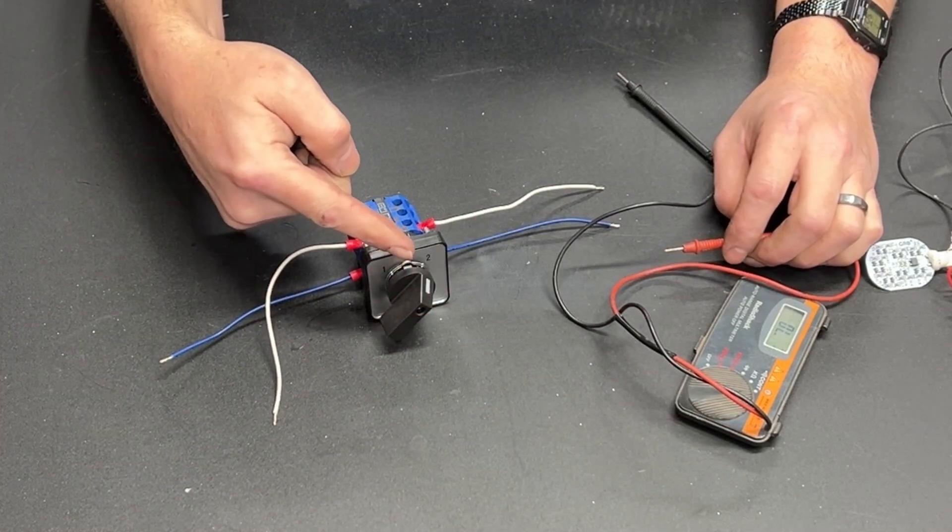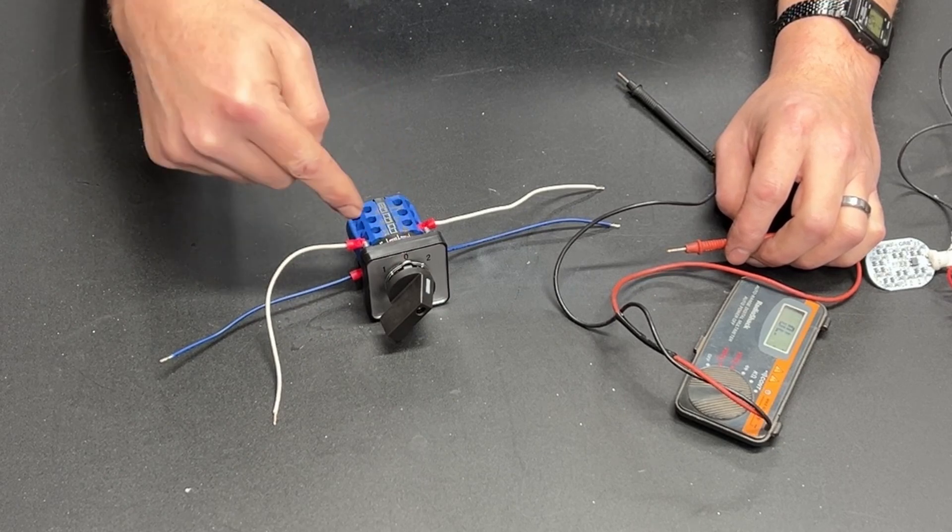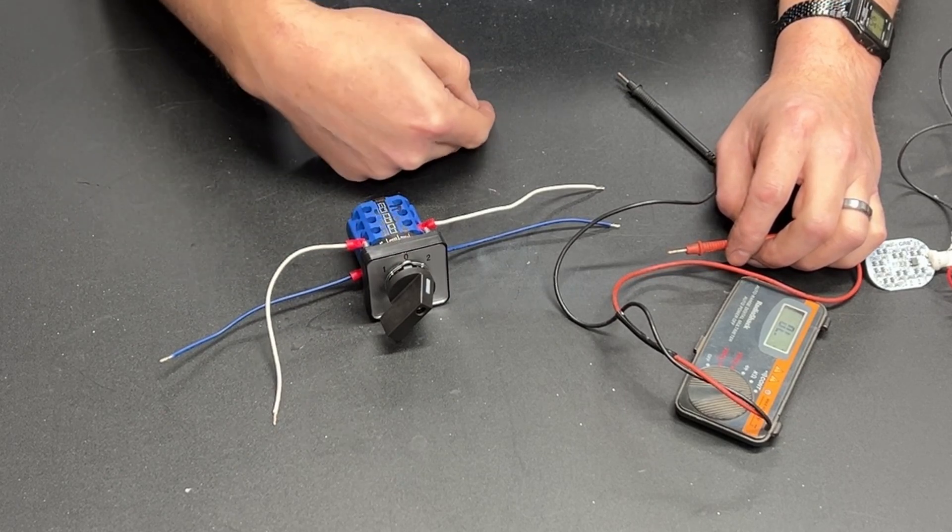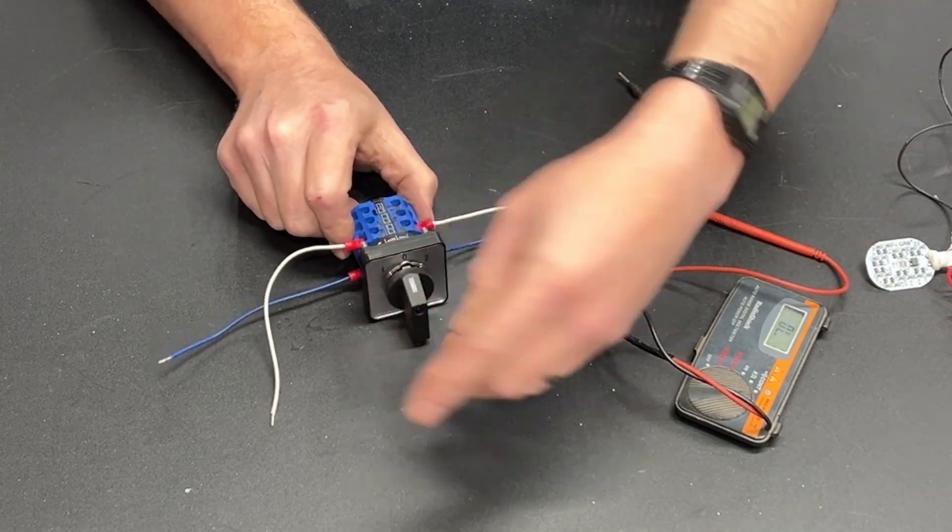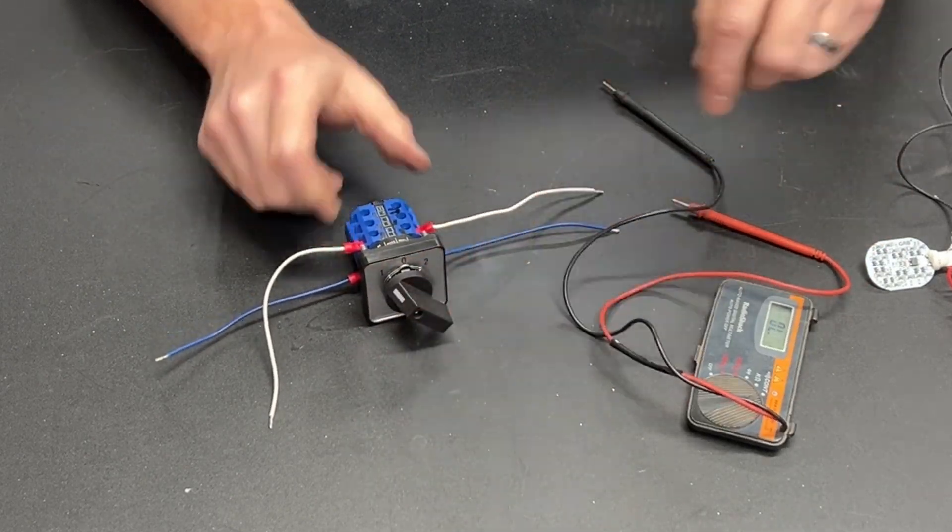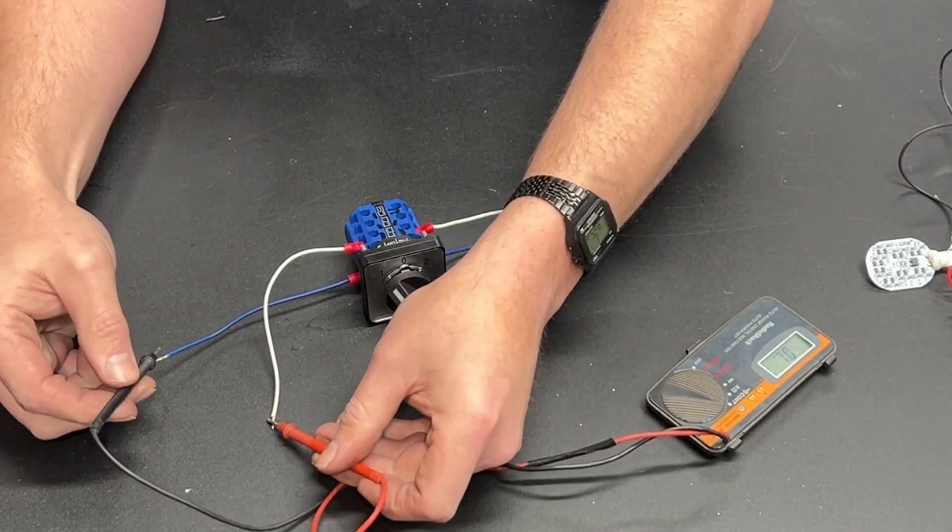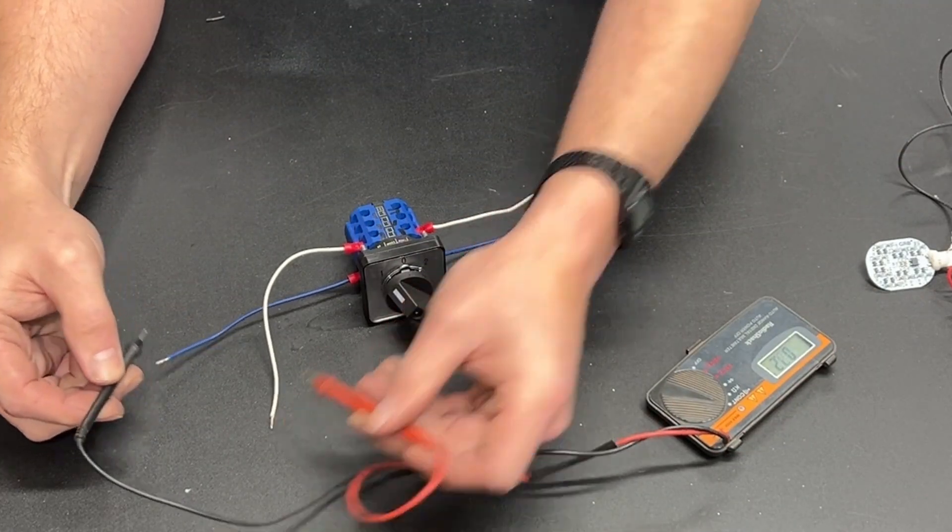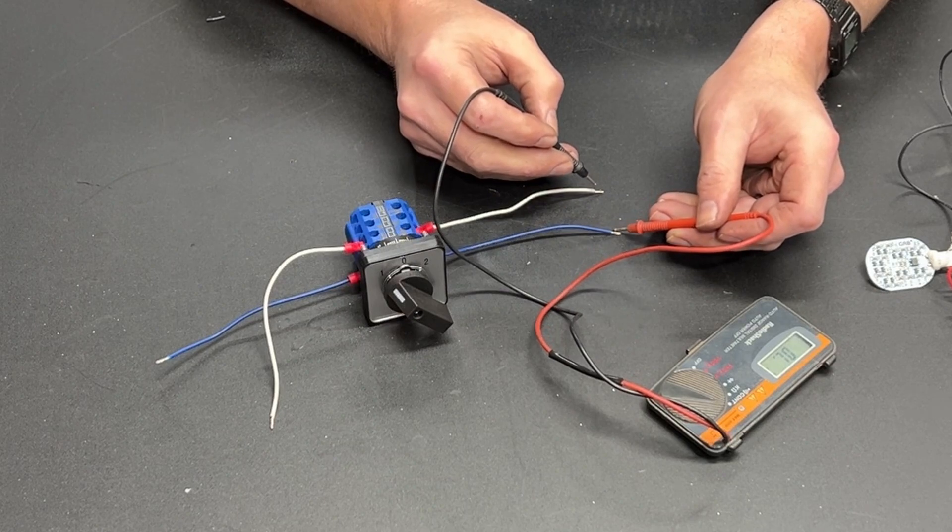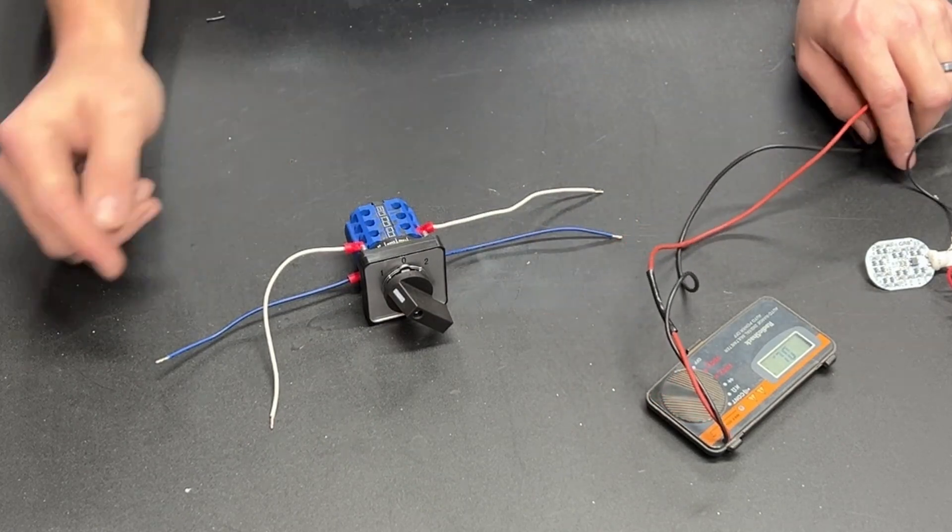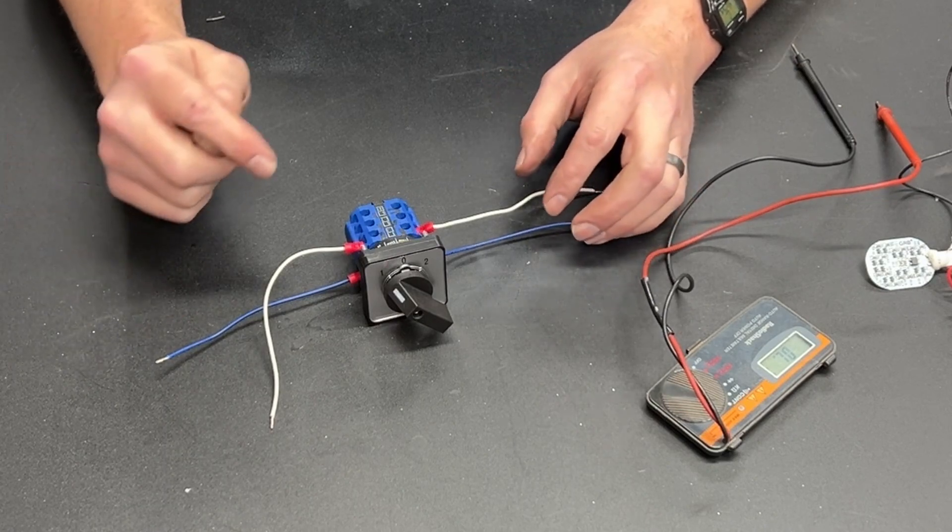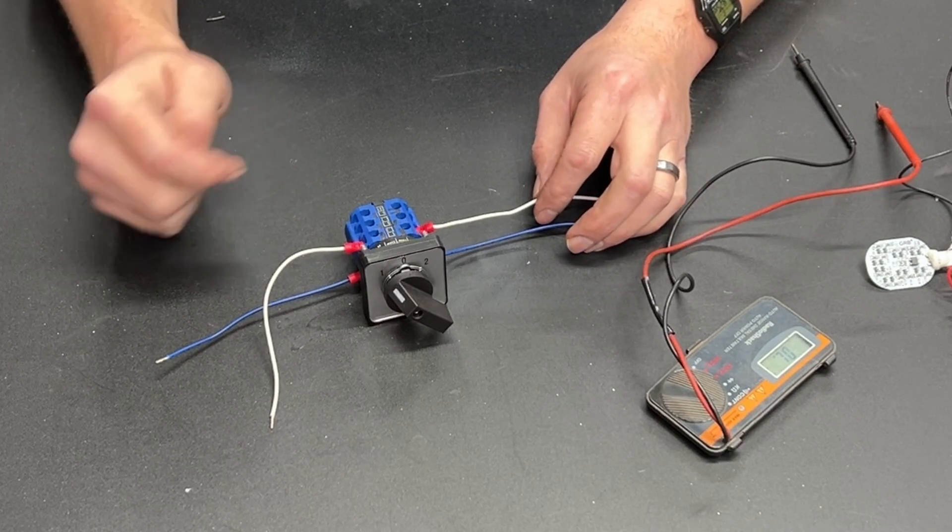So basically this changeover switch, there are three banks of switches here and it turns all three of them on. But it does nothing for this side. We go back to center off. We go the other direction. Now we have continuity. Again if we come and touch these wires we don't have continuity. That is how most changeover switches work.